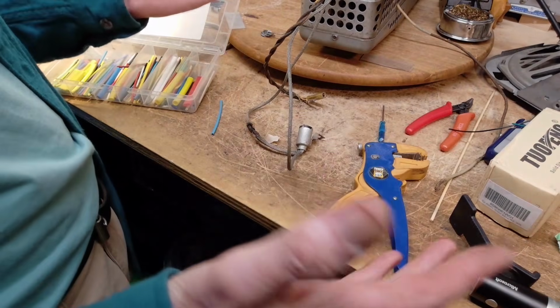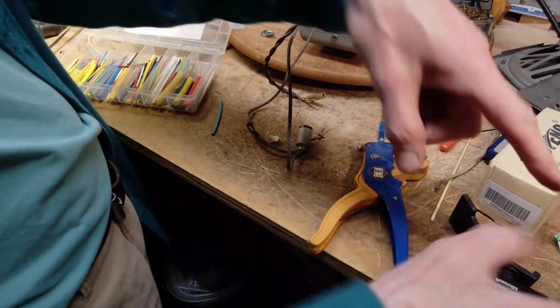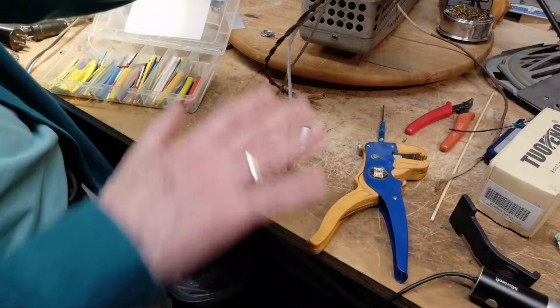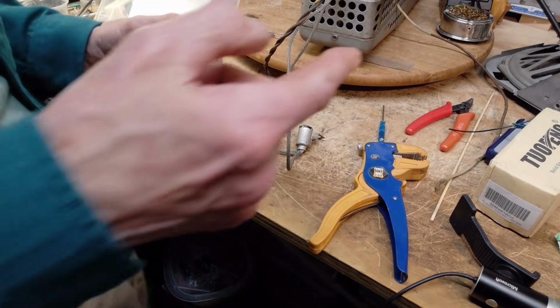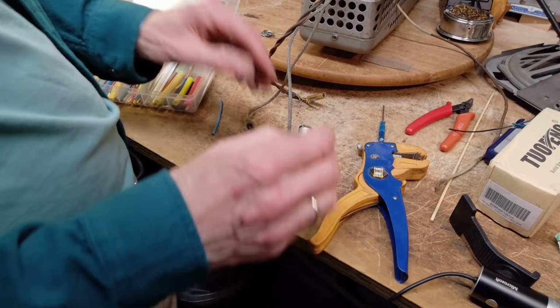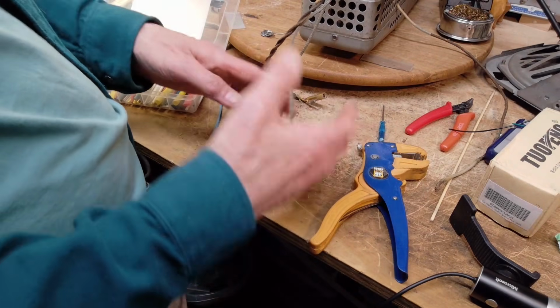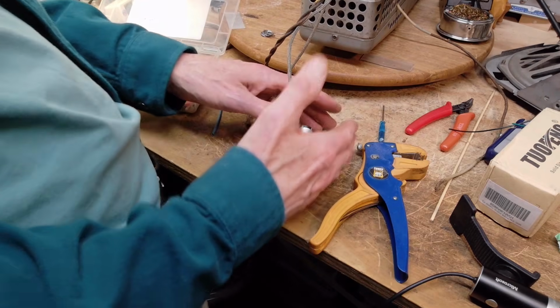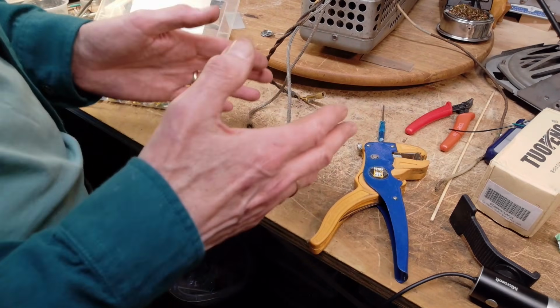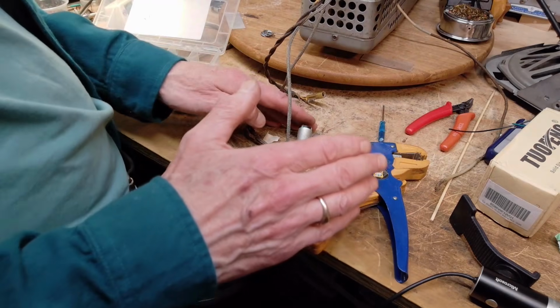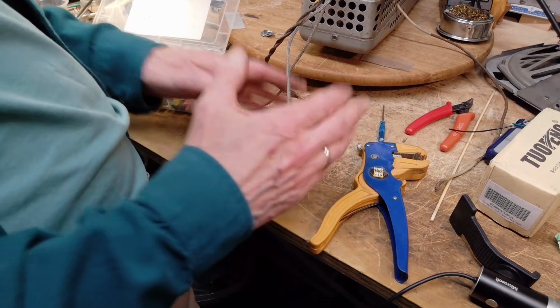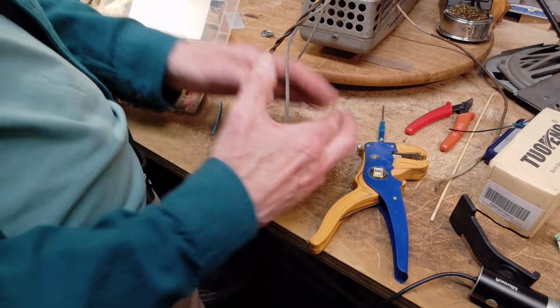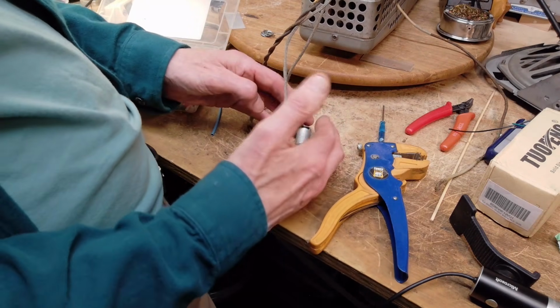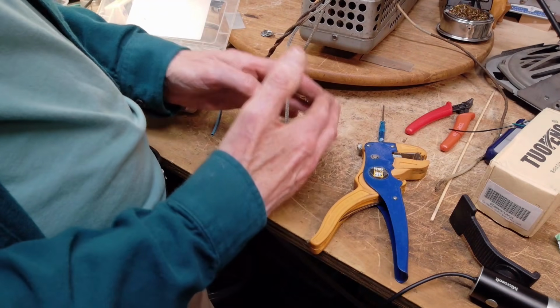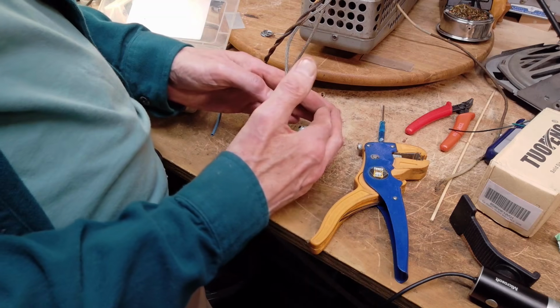So the deal is, you set something like that up, oh my god, you have all these vaults with these big transformers, 500 kVA transformers, big powerful transformers, all energized from different high voltage feeders. The whole thing's set up so the load is all balanced, and one of the cables fails. Let's say on the secondary side, the low voltage cables, 120, 208 volt cable fails. The amount of power that's available to go into that fault - I'm not saying all this power would show up, but in certain circumstances you'd get something like what I'm going to describe - the amount of power that can be present in the fault, which is going to last 2-3 cycles maybe, is equivalent to 1/3 of the entire load of the city.